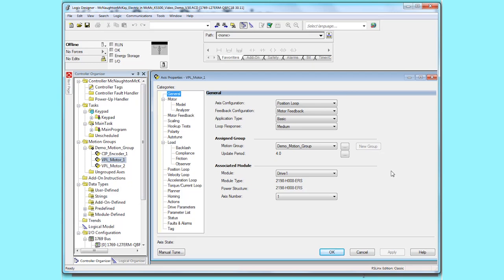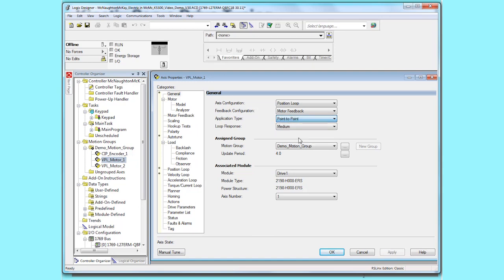We'll go to the general tab or general category and we'll select the application type, which defaults to basic. We'll change it to either point to point or tracking, whichever your application is. This application is a point to point application. You'll notice that four asterisks appear on the left hand side of the menu bar. This means that values in these fields have changed. We'll click apply to accept those changes.